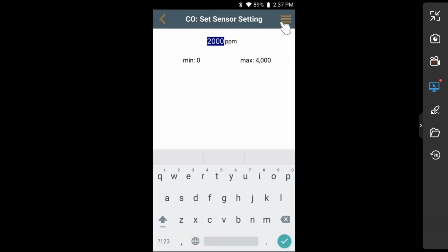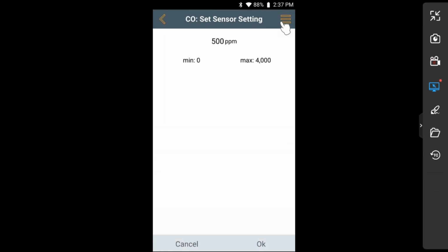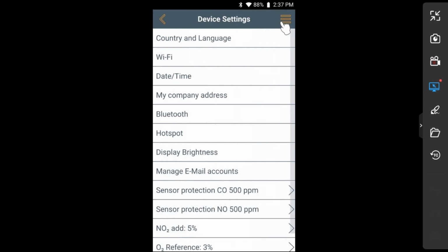The instrument CO sensor goes up to 4,000 parts per million. I can change that so that the instrument shuts itself off after 1,000, 2,000, whatever number I put in there. I could shut it off at 500 ppm if I want to, and press OK. Now it's telling me that my instrument is going to shut off at 500 ppm when it sees over 500 ppm. The reason why I'm showing you this is because the CO sensors are very accurate sensors down to 5, 10, 3 parts per million.